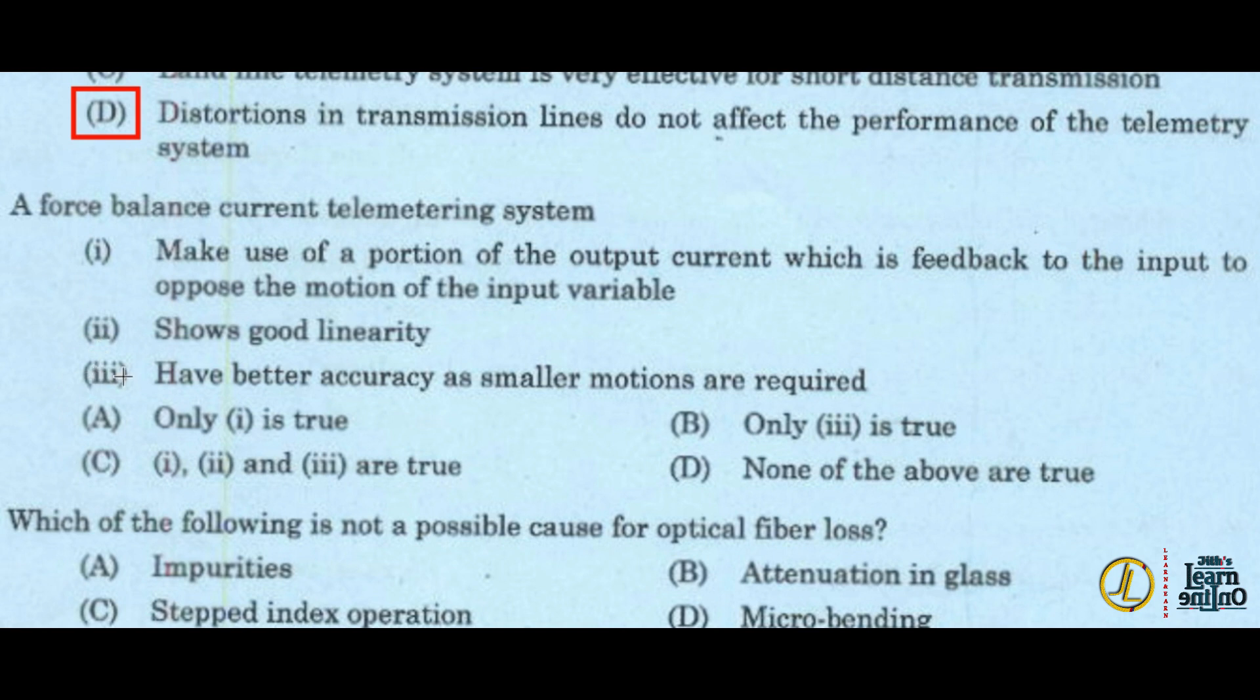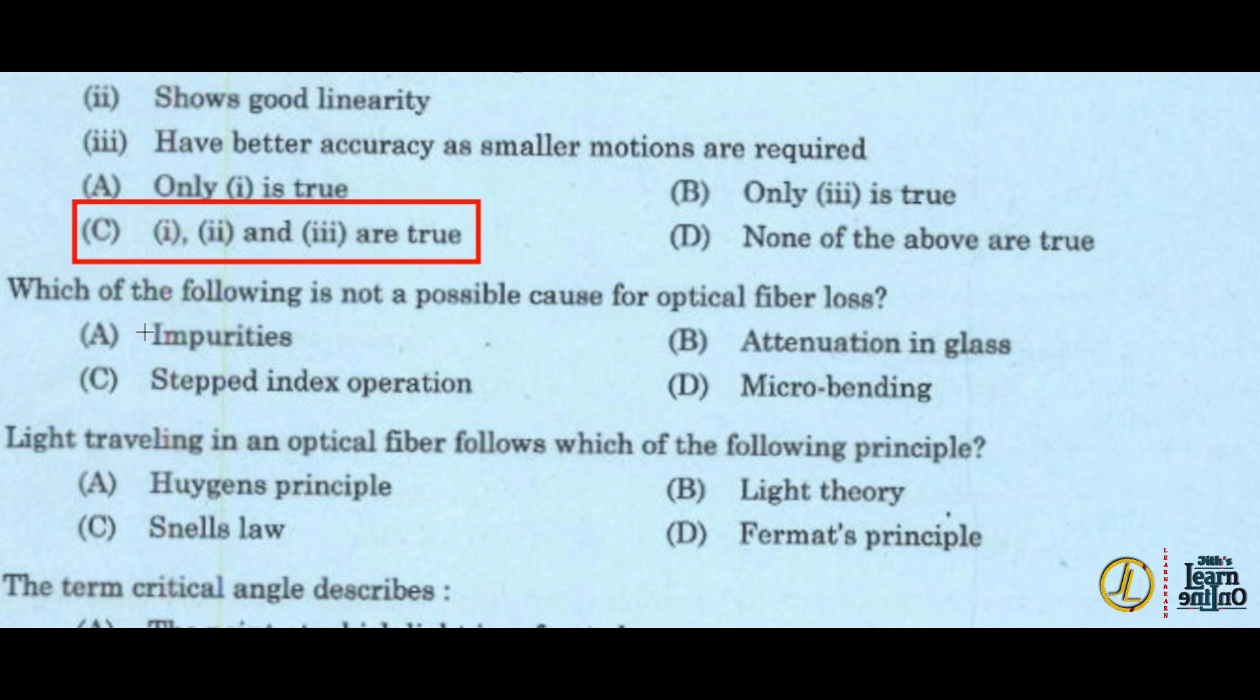A force balance current telemetry system: one, two, three are true. Option C is the answer. One, make use of portion of the output current which is fed back to the input to oppose the motion of the input variable. Two, shows good linearity. Three, have better accuracy as smaller motion are required. One, two, three are true.